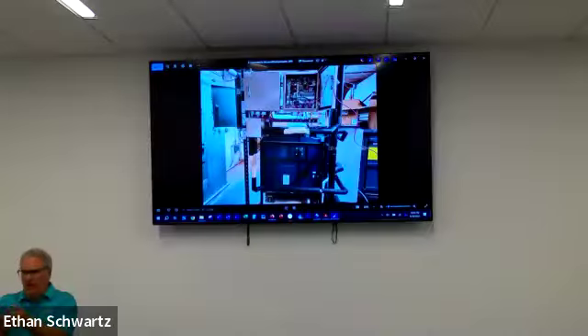There are 2 separate circuits, there's no connection between them, so we have an interlaced coil. Let's say 20 tons and 20 tons for 40 tons. And this one is staged up a little bit higher, a little bit higher setting. So it starts to drop back and then drop off, and then this one continues on. That's why we don't have that problem. The others are tying them together and bringing them all down, which in reality is not really what happens, because part of the situation is, what's happening in the building? And what does that return air look like?